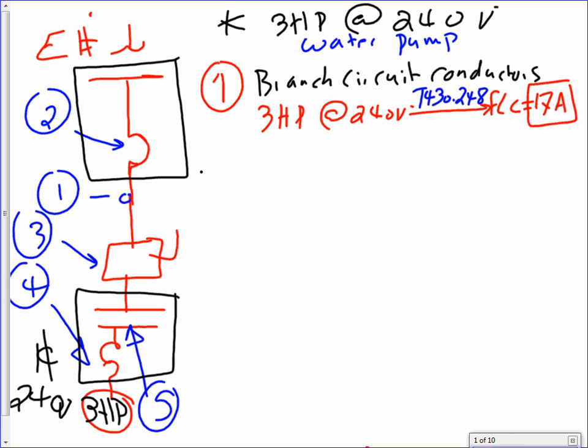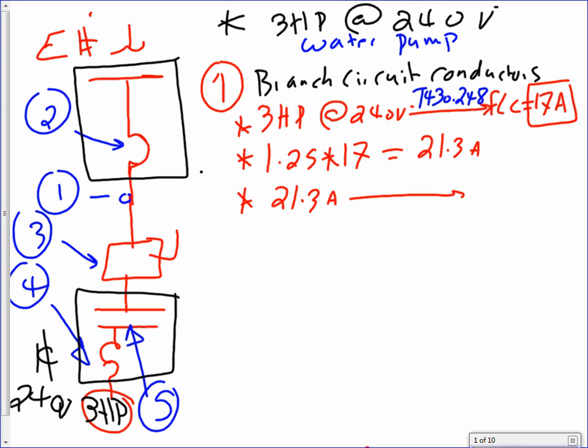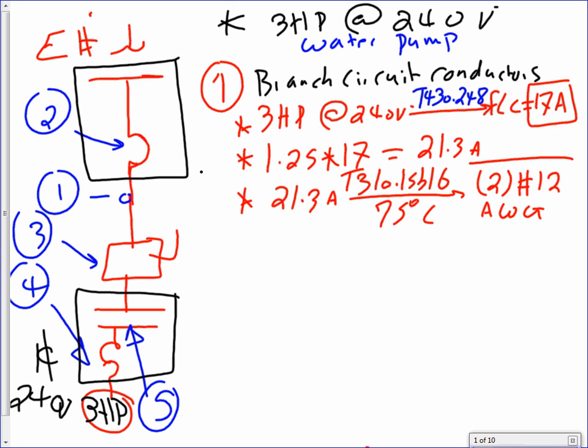Then the next, the NEC code book, guys, says motors are continuous load. Then when we size the conductors, 1.25 multiplied by 17, because it's continuous load, will get me 21.3 amps. And then you take the 21.3 amps and take it to table 310.15 B16. These are branch circuits under the 75-degree column because they're motors, and that will give me two conductors number 12 AWG. Two conductors number 12 AWG.